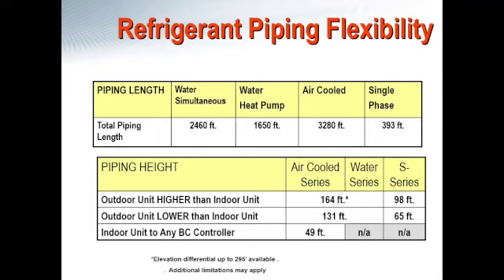These numbers have actually been updated slightly on the piping height difference. But for now, we'll just say that if your outdoor unit is higher than your indoor units, you have 164 feet of vertical separation capability. And if your outdoor unit is going to be lower than your indoor unit, you have 131 feet. Realistically, that's just a function of working with gravity.